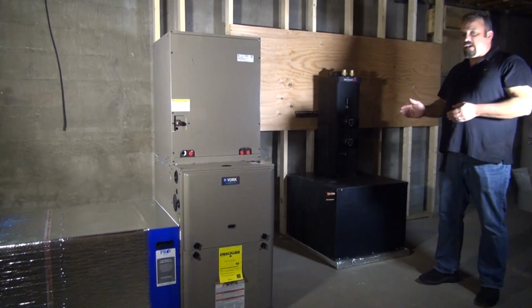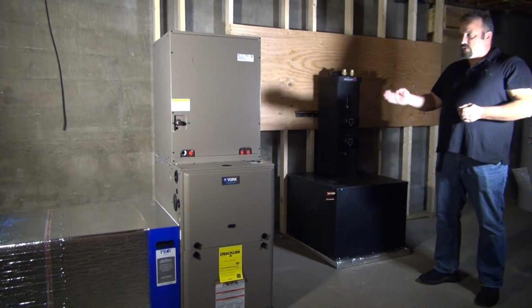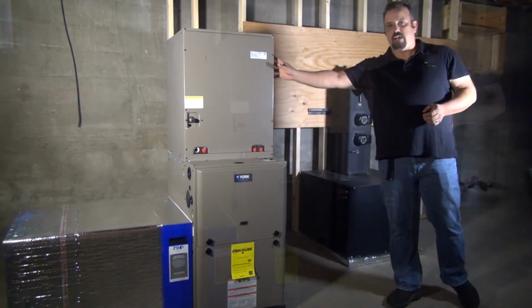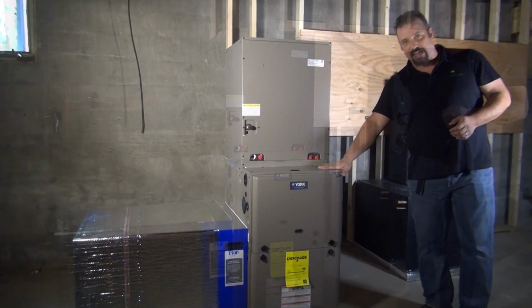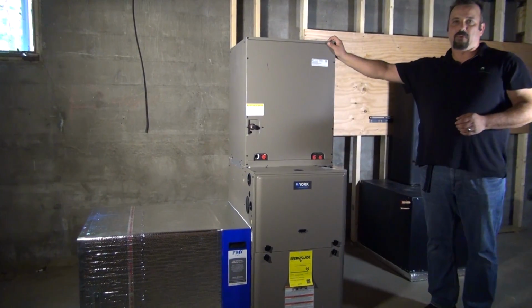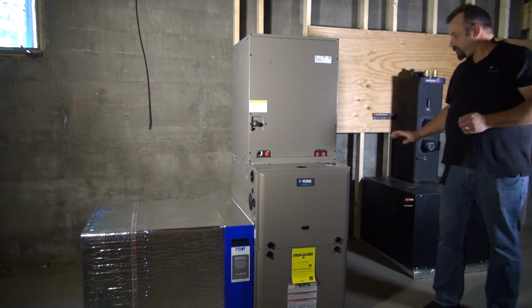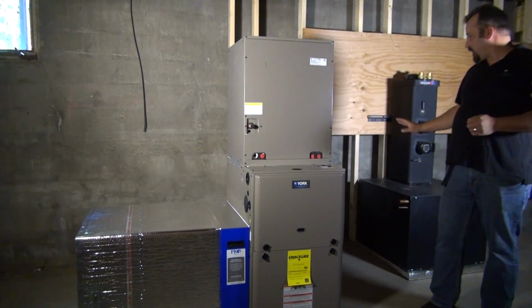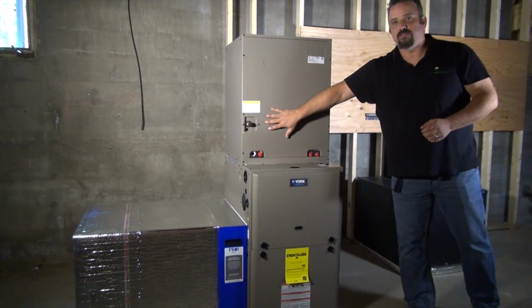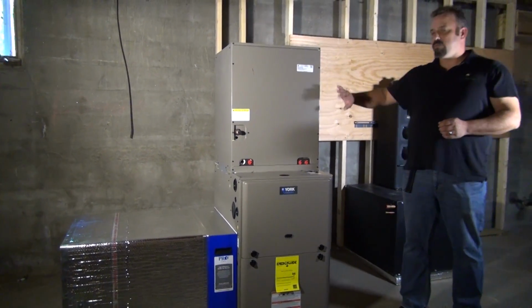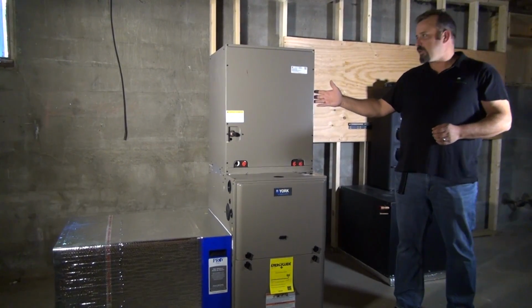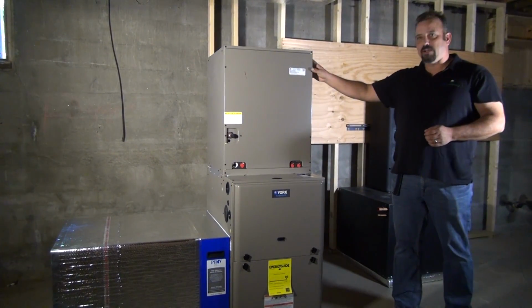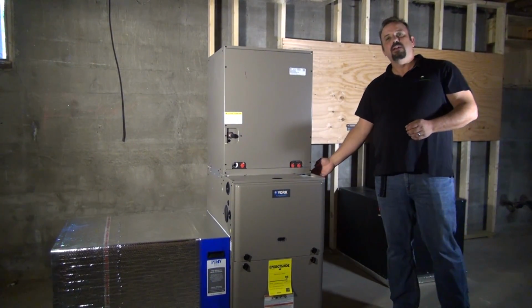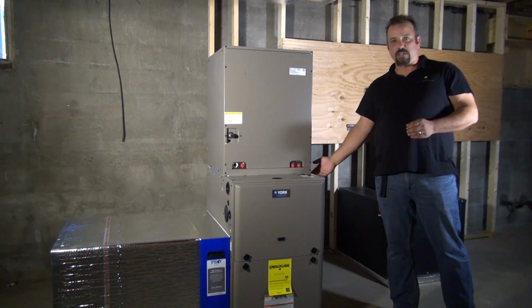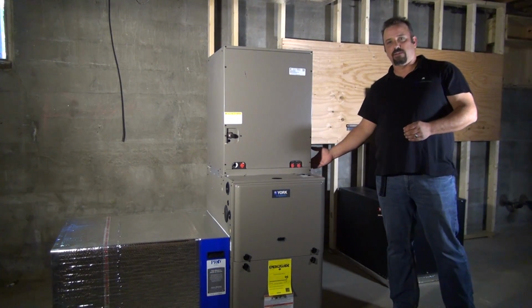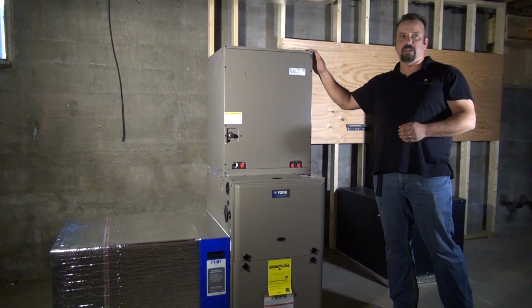We are going to be tying this geothermal heat pump into this gas furnace. This is the gas furnace, and this is an evaporator coil. The geothermal heat pump is going to connect from here to this evaporator coil. So your heating and cooling via your refrigerant will be done inside here, and we will be using the electronically commutated motor, or ECM motor, from this as an air handler to put the heating and cooling into the home.